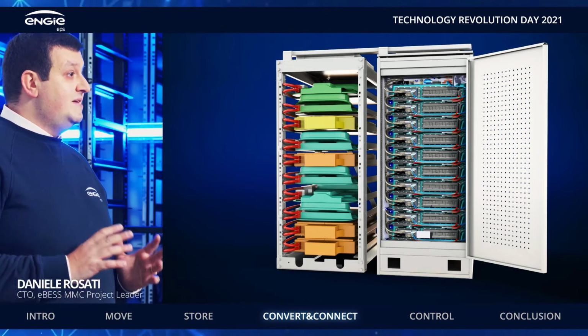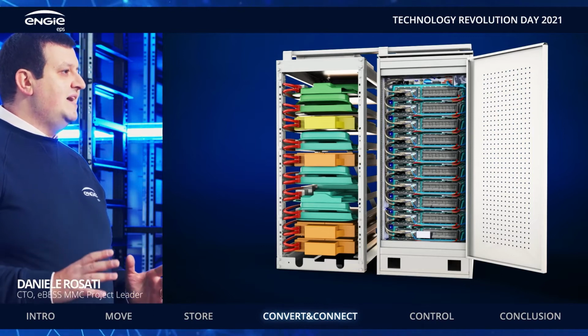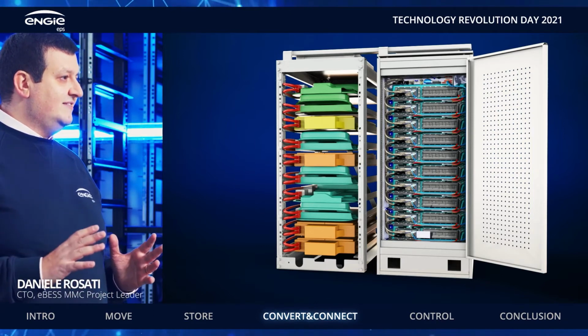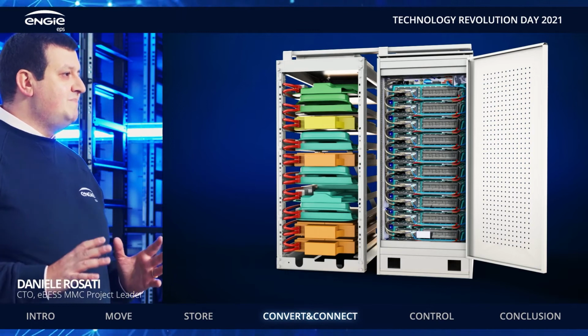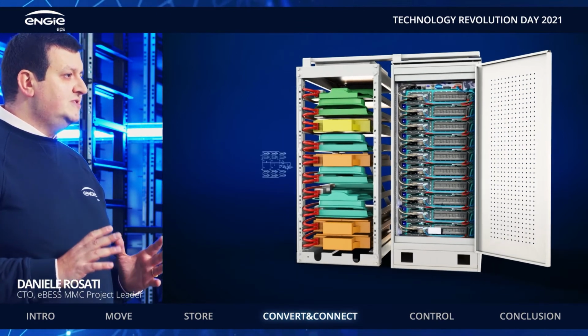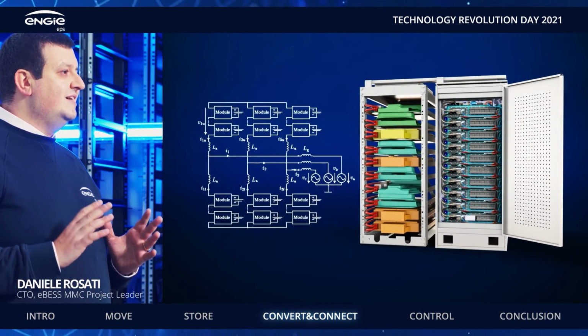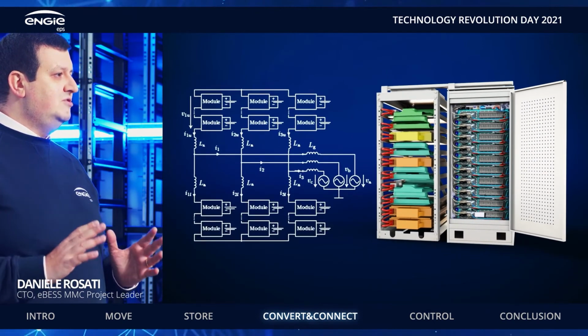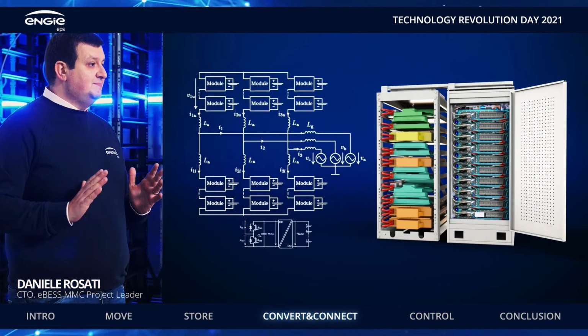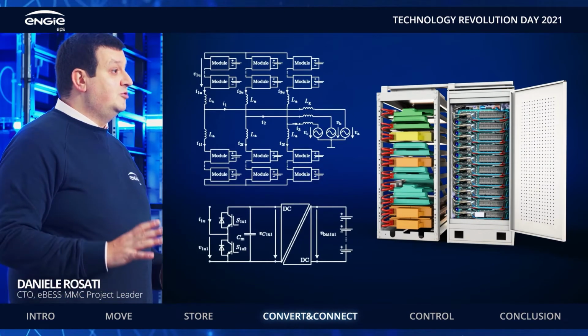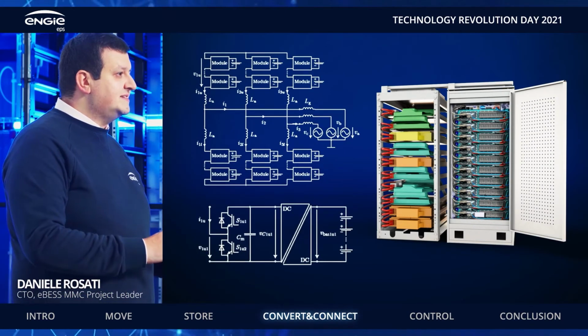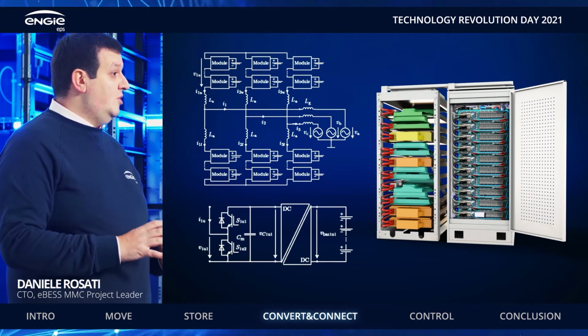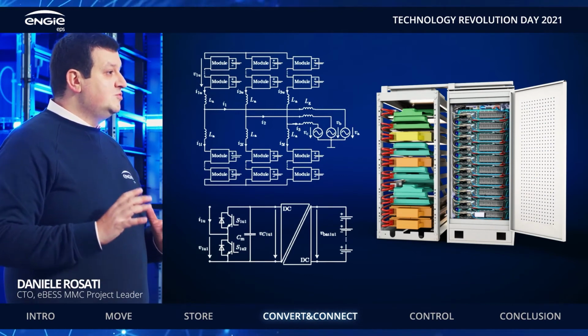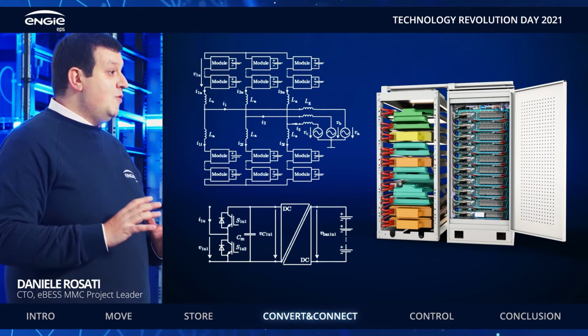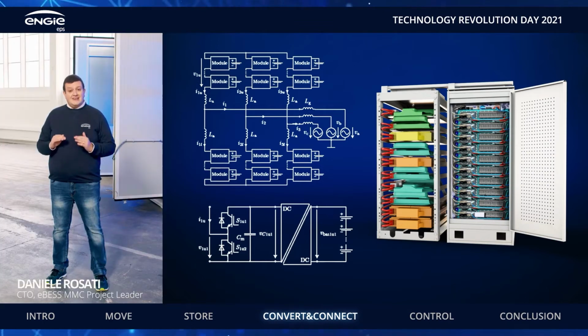The modules will be medium-frequency SiC technology-based AC-DC power converters with independent DC buses and AC outputs series-connected to directly create a 3-phase medium voltage output. Thanks to the MMC topology, and particularly to the medium frequency small transformers placed into the converter modules, full galvanic insulation will be guaranteed, and we will propose solutions without classic low frequency step-up transformers.